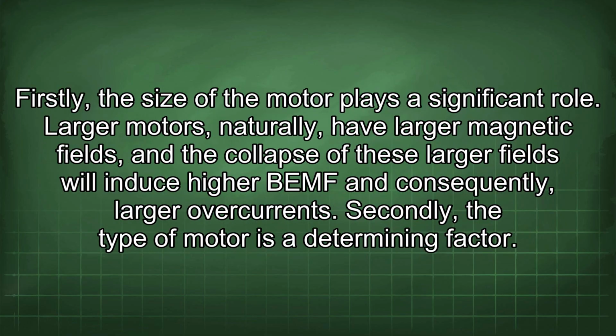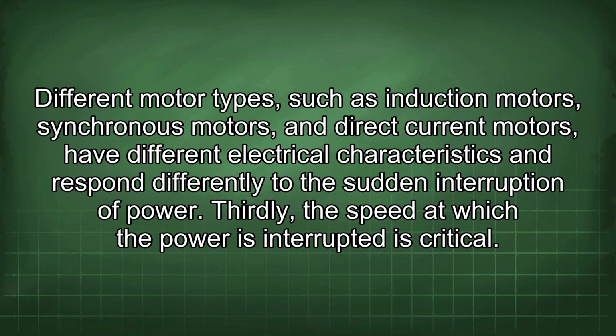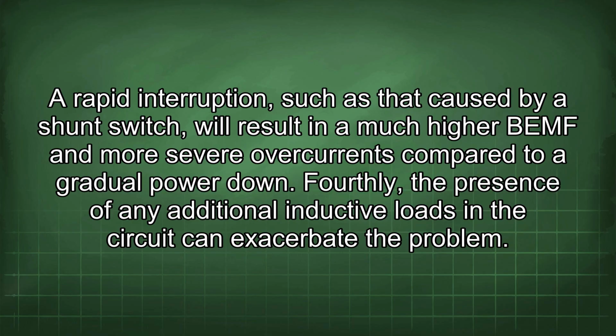Firstly, the size of the motor plays a significant role. Larger motors, naturally, have larger magnetic fields, and a collapse of these larger fields will induce higher BEMF and consequently, larger overcurrents. Secondly, the type of motor is a determining factor. Different motor types, such as induction motors, synchronous motors, and direct current motors, have different electrical characteristics and respond differently to the sudden interruption of power. Thirdly, the speed at which the power is interrupted is critical. A rapid interruption, such as that caused by a shunt switch, will result in a much higher BEMF and more severe overcurrents compared to a gradual power down.